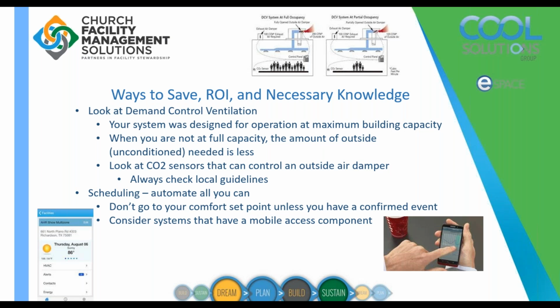If we're able to limit the outside air to only bring it in when we need it, our equipment can operate that much more efficiently, and it saves us quite a bit of money. Especially if you're in a humid region, we're not bringing in that humid air. It makes your building feel cooler, feel better. As always, check your local guidelines to make sure your codes allow it. But most places can do that, and you can set it independent of your other system. Again, it just takes monitoring the CO2 levels in your main occupied spaces. And if at some point you want a nice, easy 60-page read on demand control ventilation, let me know, because I have one. It's a great engineering document that explains it and some of the advantages of that.